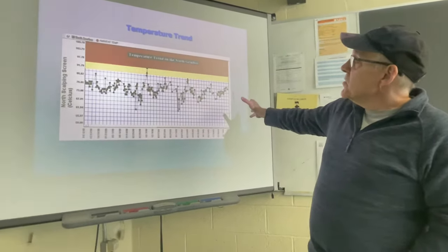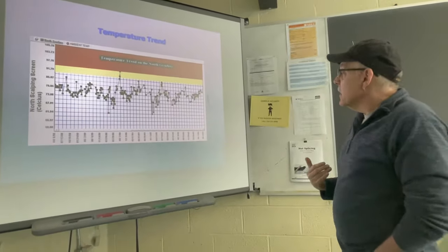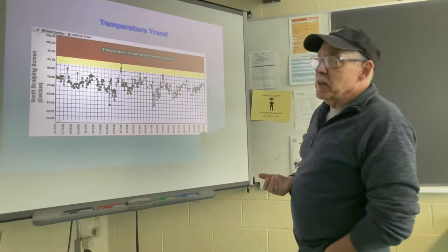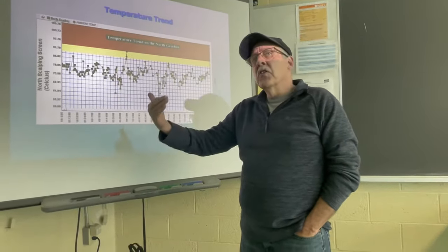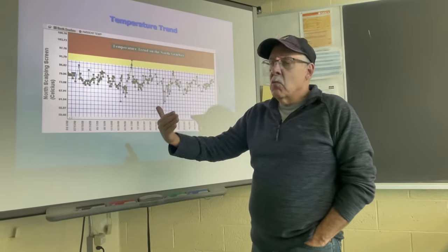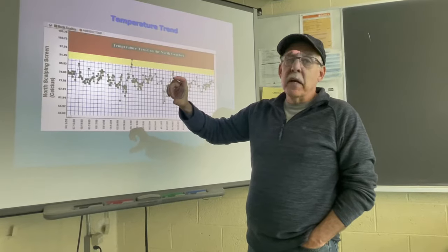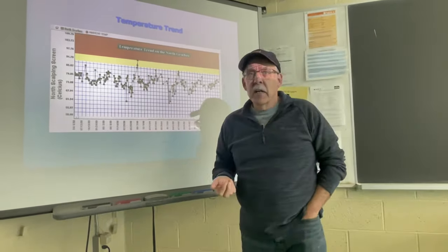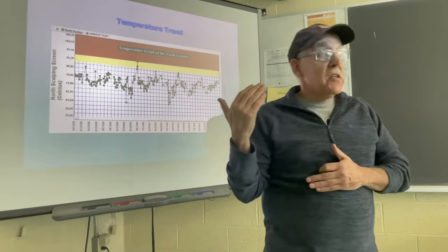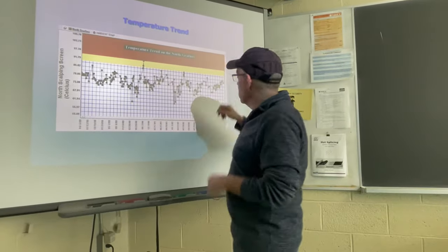So the first thing that we did, and this is what alerted the guys to the problem here, is they go out and we do something called basic care in industry. Basic care is kind of like a vibration program, but what we do is have people go out and use a little vibration pencil, that little overall meter, and a heat gun, and once a week they'll take a vibration reading to see if it's vibrating more than it was last week, and they trend the temperature so we can see any spikes in temperature.